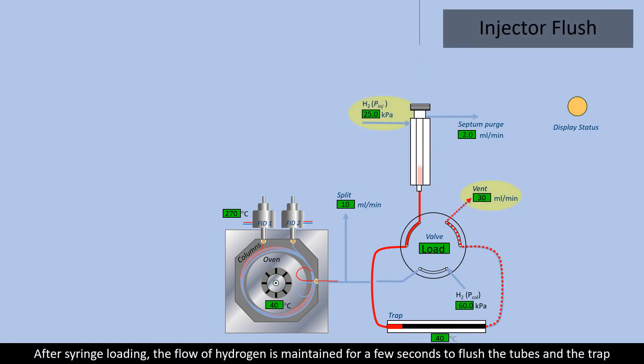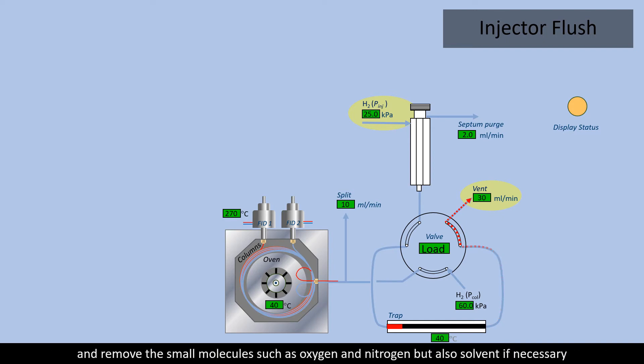After syringe loading, the flow of hydrogen is maintained for a few seconds to flush the tubes and the trap, and removes the small molecules such as oxygen and nitrogen, but also solvent if necessary.